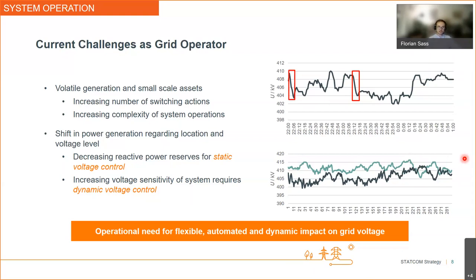So to manage these new challenges in system operations, we need to face the decreasing reactive power reserves regarding static voltage control, and we also have to tackle the problem of increasing voltage sensitivity of the system by means of dynamic voltage control. So to sum it up, in system operation, we have a high and increasing need for flexible, automated and dynamic impact on the voltage control.